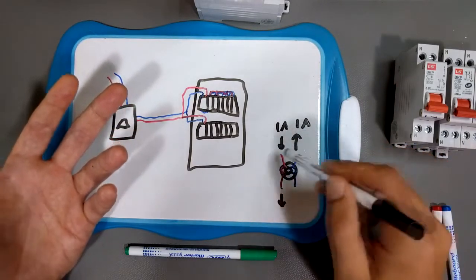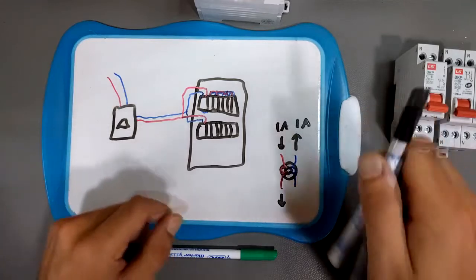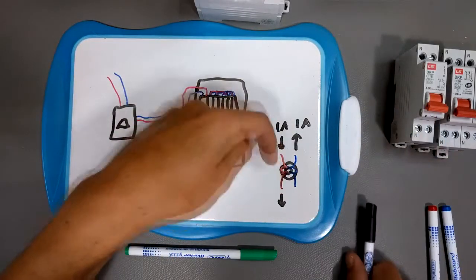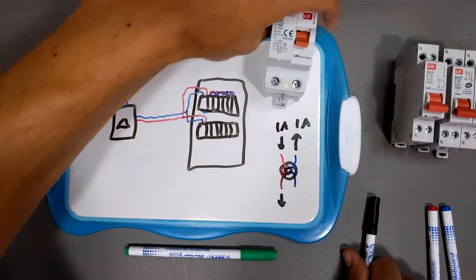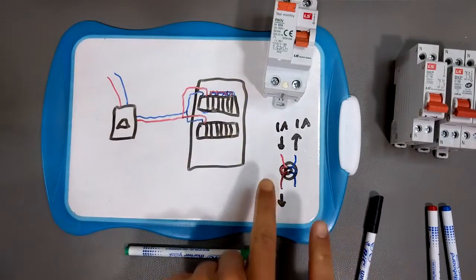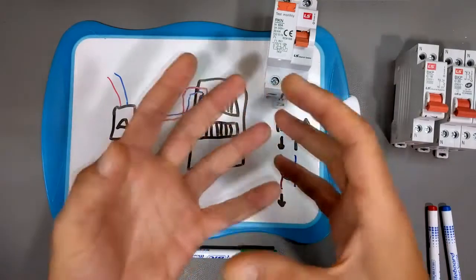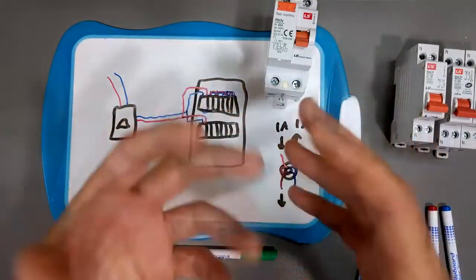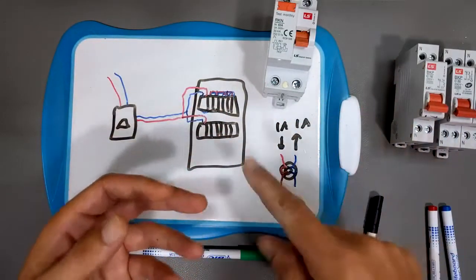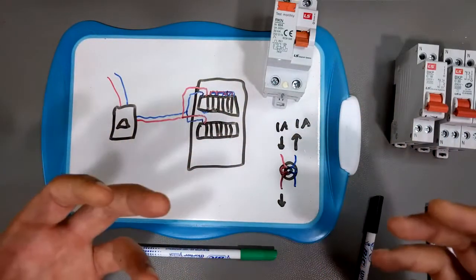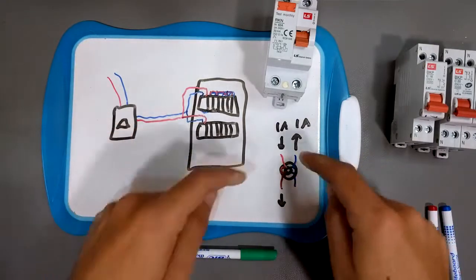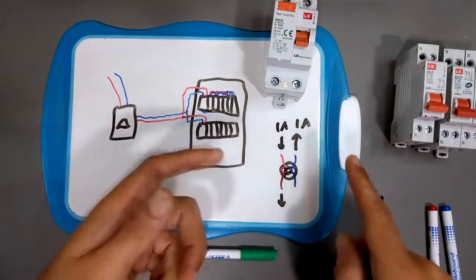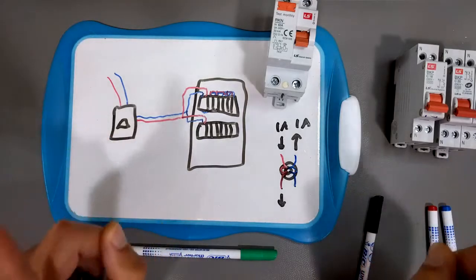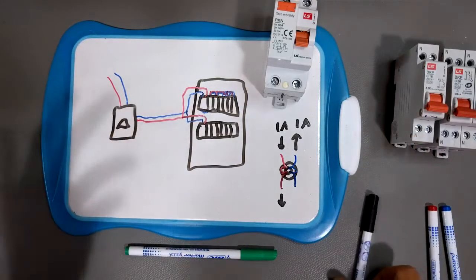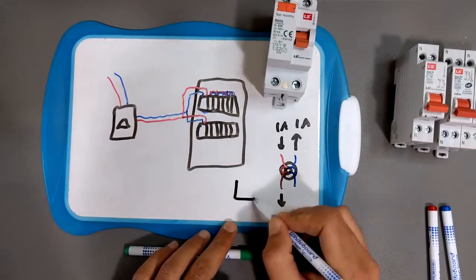So you're operating your gizmo at a certain voltage. If you've got 1 amp going through this differential breaker and into your gizmo or power outlet, the same amount of current is coming back. Even if your gizmo is, say, a fan consuming power and performing some work like rotating, the current going in is always going to be the same as the current going out, unless there's a fault condition. So let's say you have your gizmo...